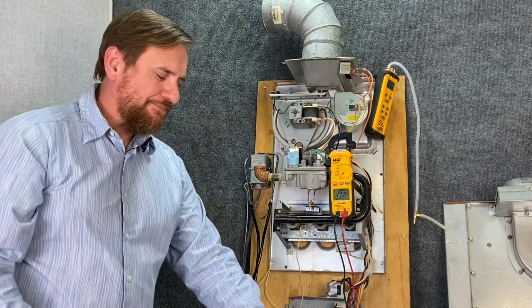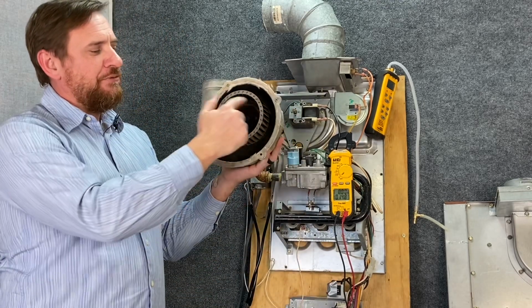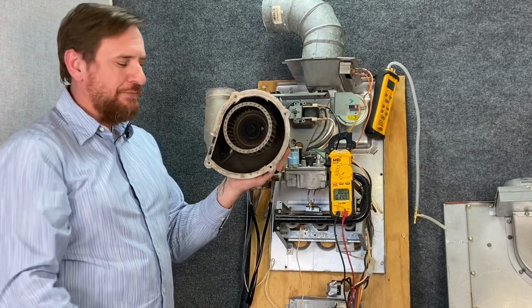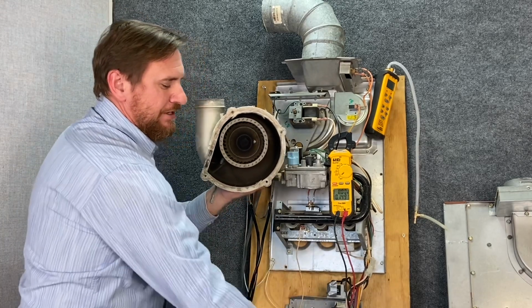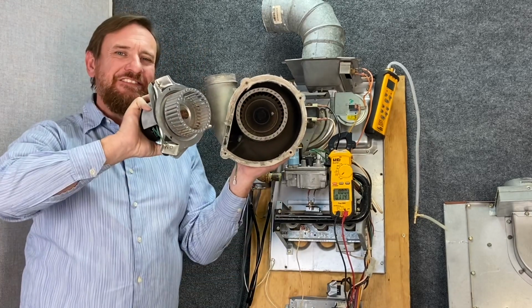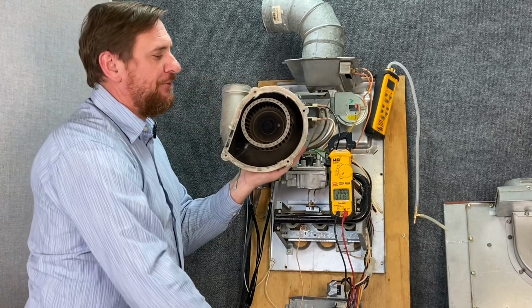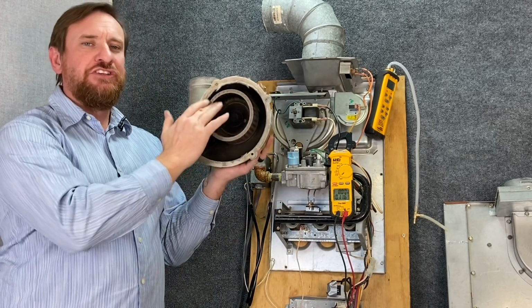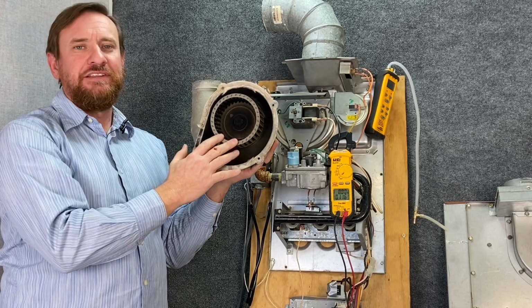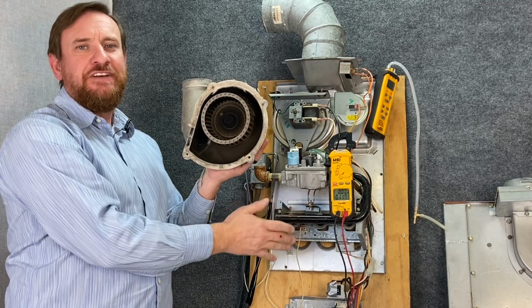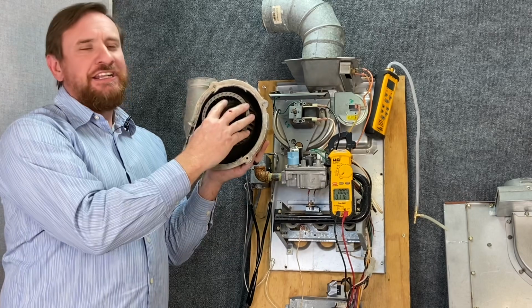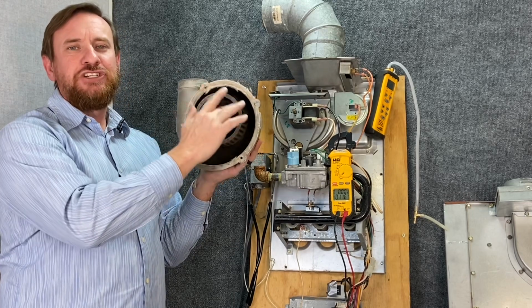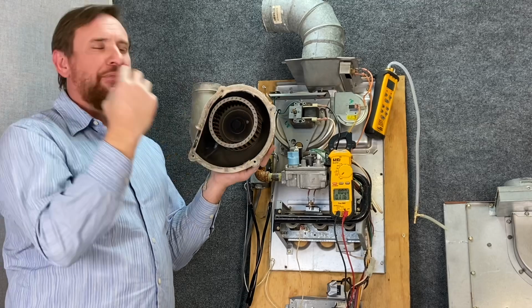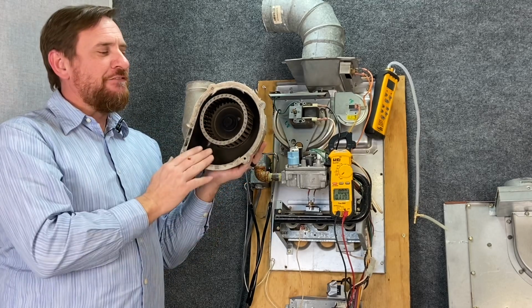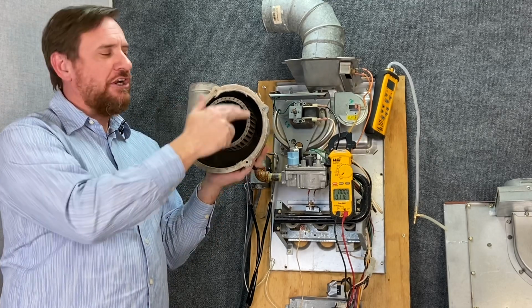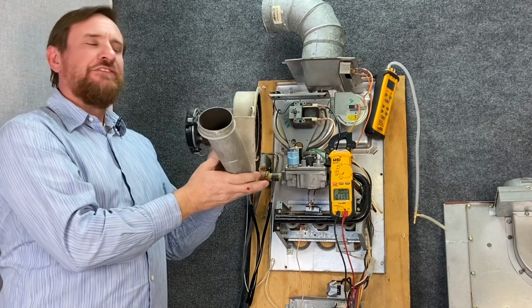Another example we have is this one. Notice it's very sooted up, extremely black. We compare it to this one, and we can see a significant difference in the condition of this blower wheel. What happened with this particular situation was the furnace was running on propane. The furnaces come naturally from the factory for natural gas. Running this on propane gives you the improper air-fuel mixture, the improper spuds were used, improper gas pressure is used. Even though it ran for a short period of time, it sooted up all of this entire inducer fan assembly.